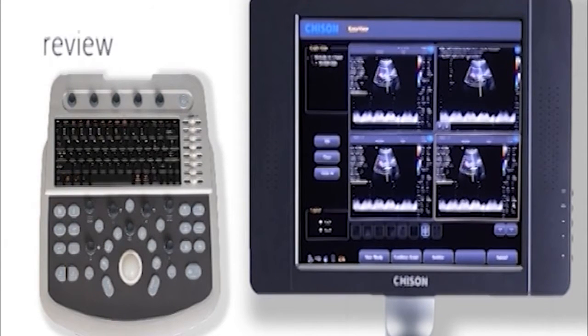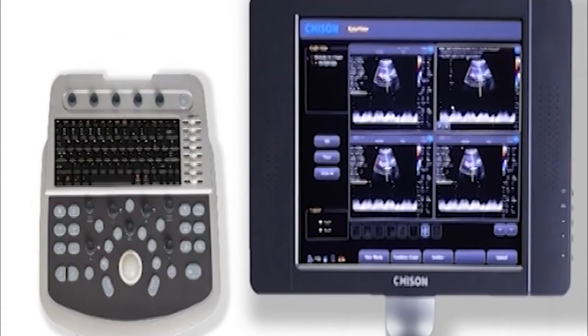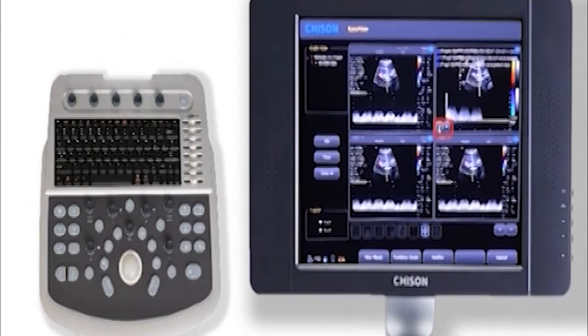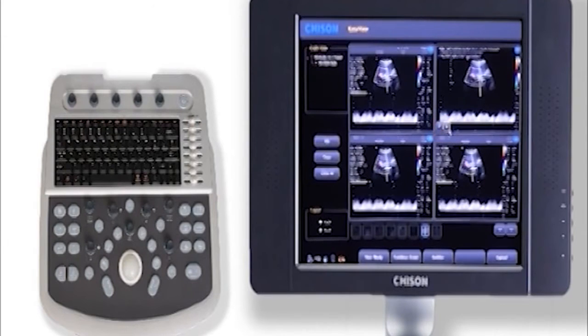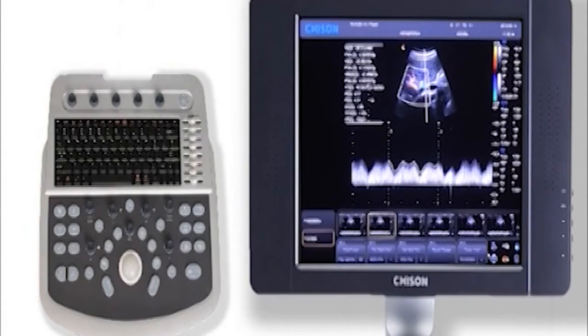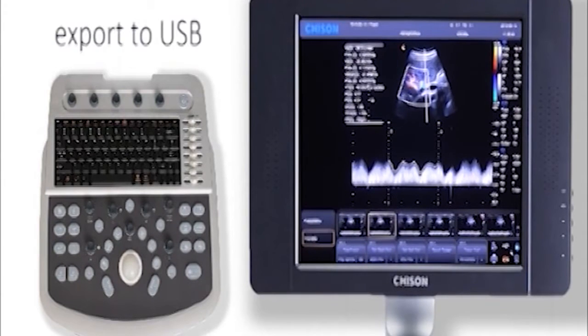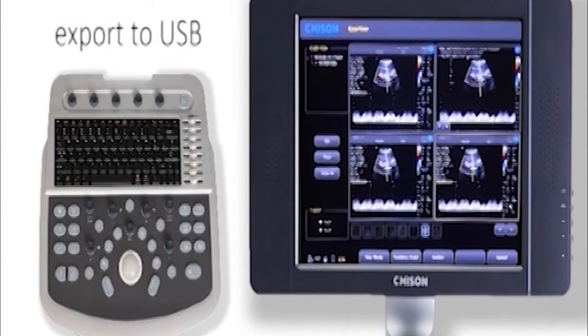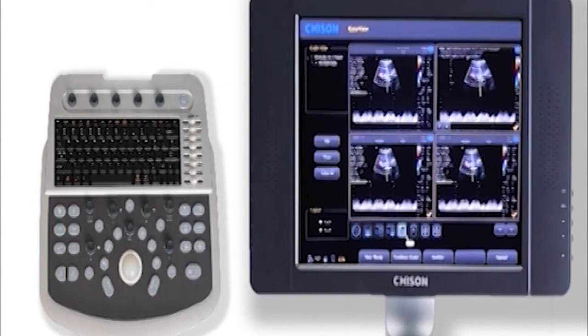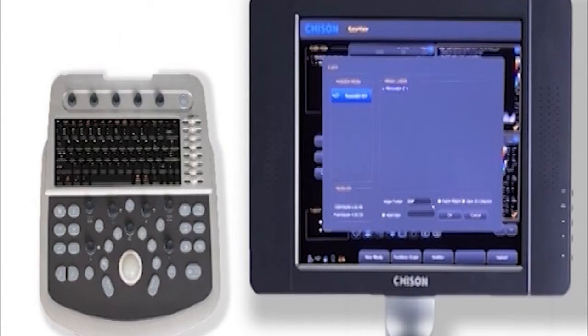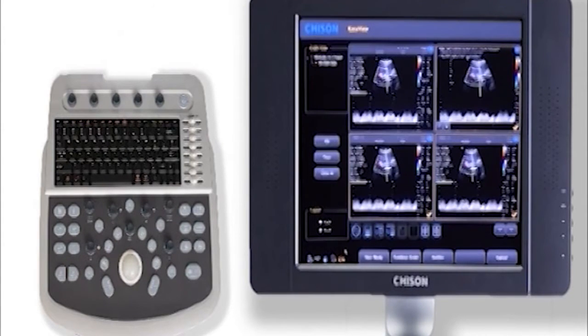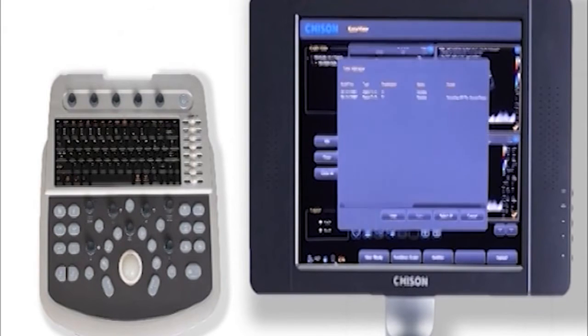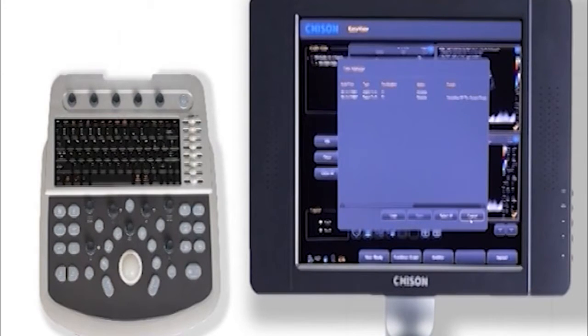When my exam is done, I can press this key to review the images from the study. You can hit play and review it, then stop. If I want to export images to USB, first plug the U-disc to the ultrasound system. Until it's recognized, select images or cine you want to copy, then click this icon, export. Select image format and 2D AVI. Finally, click OK. This little line down here indicates that images are being exported. And now you can see it's finished, so I can hit cancel.